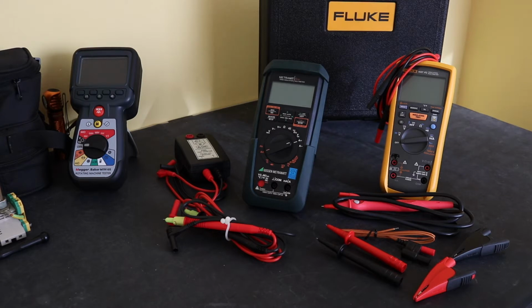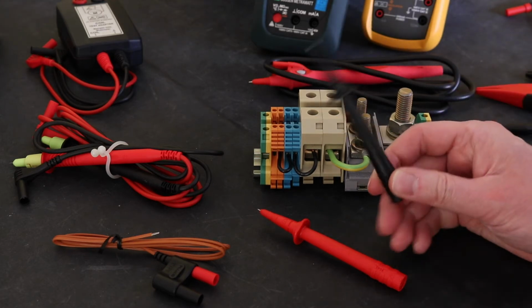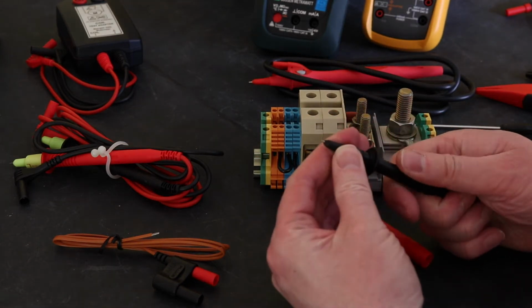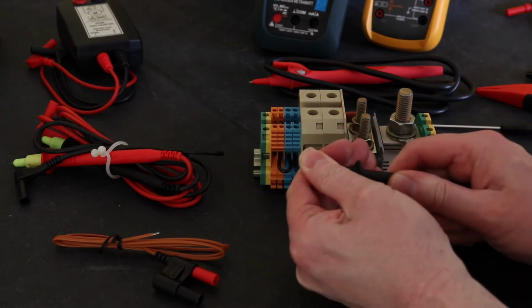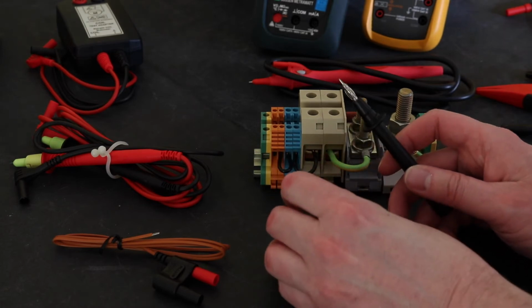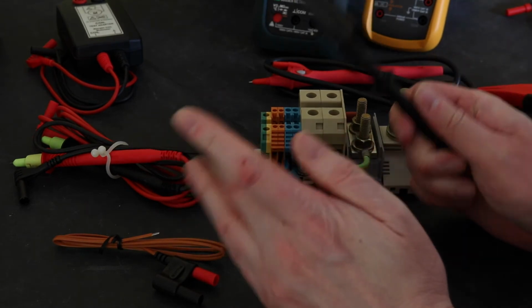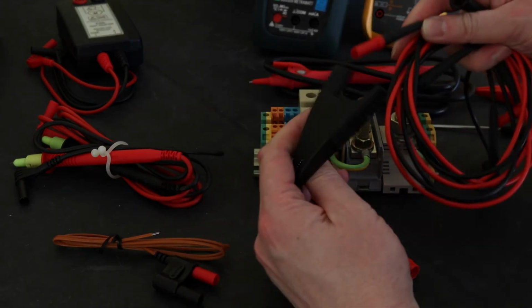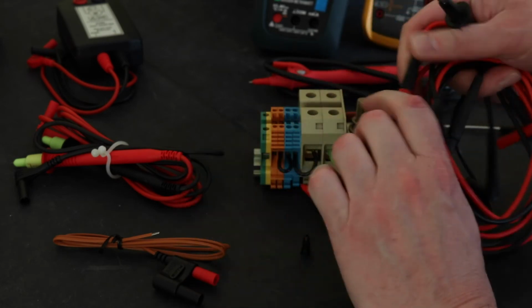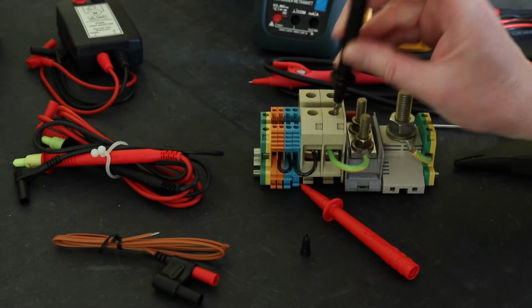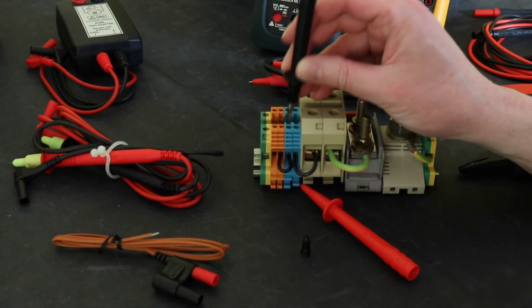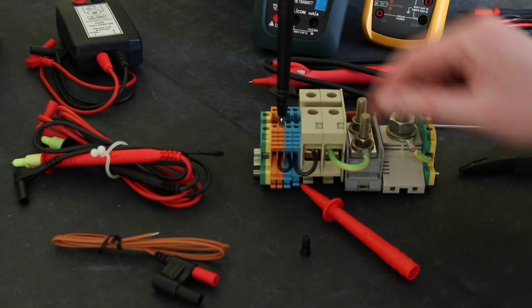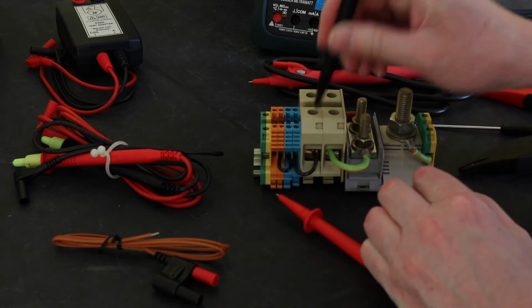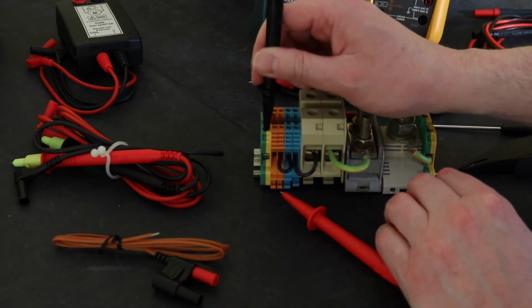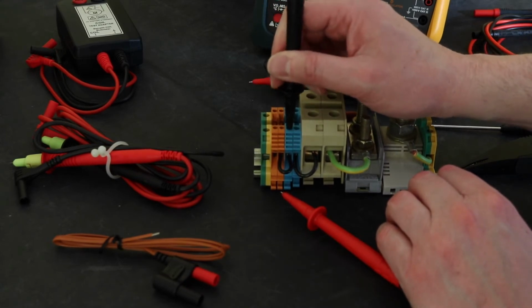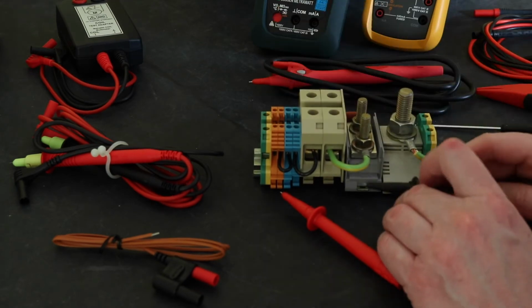Okay, so let's take a closer look at the probe arrangement for the leads. So we've seen the leads for the Fluke before. They come with these GS38 caps that are removable. Leaves you with a standard 4mm adapter that will go into the chosen accessory, but obviously with the leads being normal 4mm, you can put them straight onto the lead as well. Access to terminal wise, 35mm we're fine, and we can get into 4mm and just about 2.5 with the cap off. With the cap on, it's only the 35mm that's available. 6mm, that one is there, which is available to me. 4mm is not, can't make contact there. 2.5 is definitely out as well.